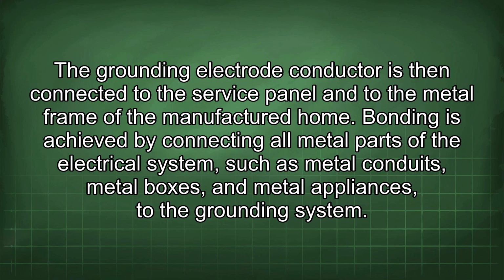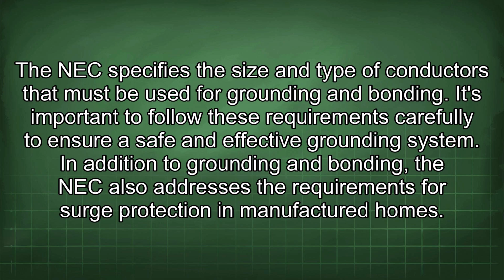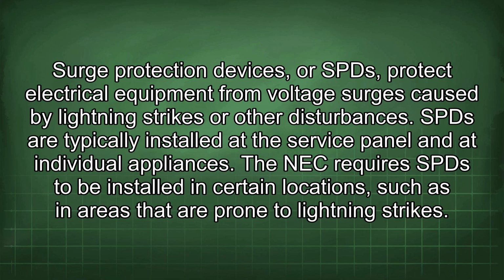Bonding is achieved by connecting all metal parts of the electrical system, such as metal conduits, metal boxes, and metal appliances, to the grounding system. The NEC specifies the size and type of conductors that must be used for grounding and bonding. It's important to follow these requirements carefully to ensure a safe and effective grounding system. In addition to grounding and bonding, the NEC also addresses the requirements for surge protection in manufactured homes. Surge protection devices, or SPDs, protect electrical equipment from voltage surges caused by lightning strikes or other disturbances.